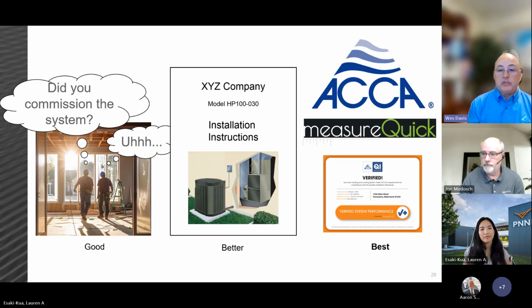ACCA and MeasureQuick have teamed up. We have a way to evaluate digitally, objectively, data from the system to tell us if the airflow, refrigerant charge, combustion efficiency, if a furnace is installed, and electrical requirements are all within the specified tolerance. And then for consumers, we have a very simple, easy to read, easy to understand certificate that demonstrates compliance is met.